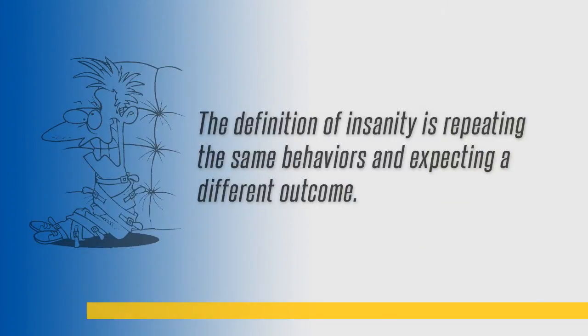If a customer keeps coming back asking for another overload, another overload — that sparks a conversation: maybe I should get in there and have a look at what you're doing so we can start saving you some money. If they're going through overloads, fuses, or breakers routinely, you have to look at what's going on. It could be an overloaded circuit, improperly sized parts, or a power quality issue. You have to go down that list to find out exactly what's happening. We can keep putting the same part in over and over, but that's the definition of insanity — doing the same thing and expecting a different result.